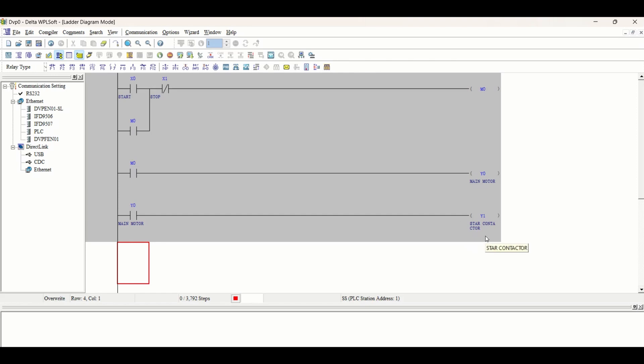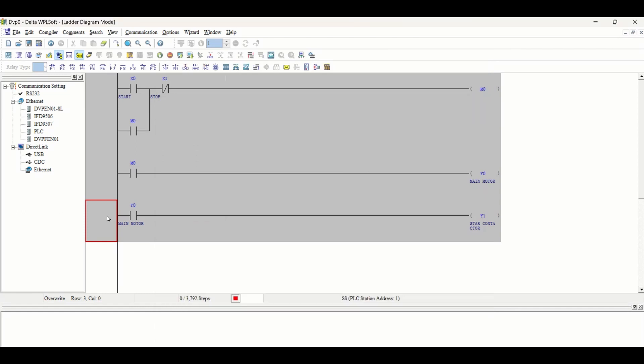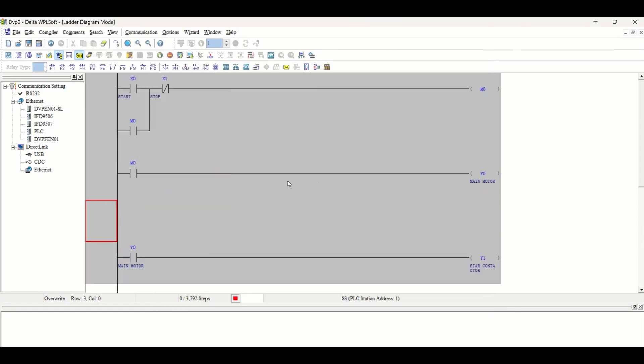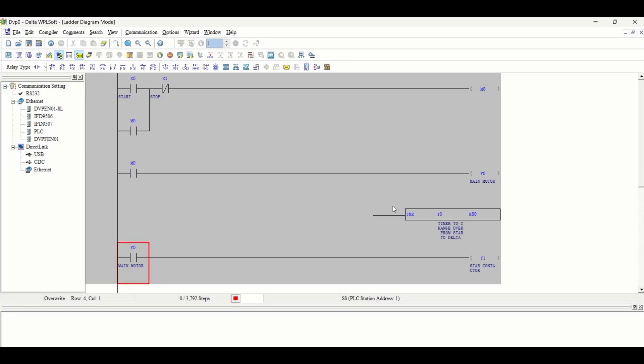After 5 or 8 seconds, we have to switch from star to delta. So with this M0, a timer should also start. Insert arrow here and take a timer TMR T0, and suppose we are taking it for 8 seconds.